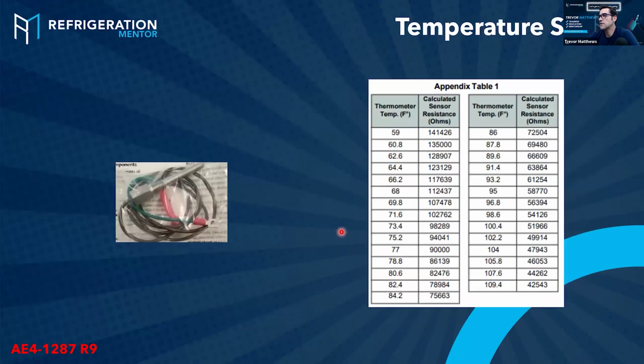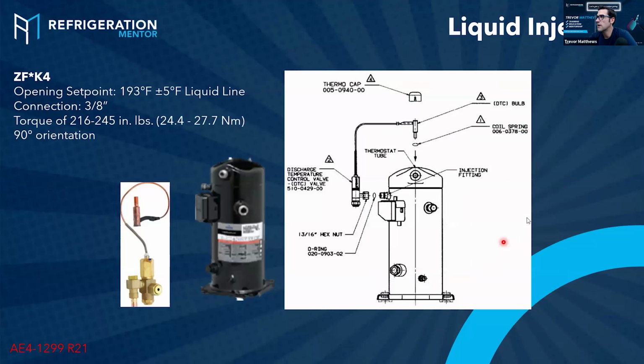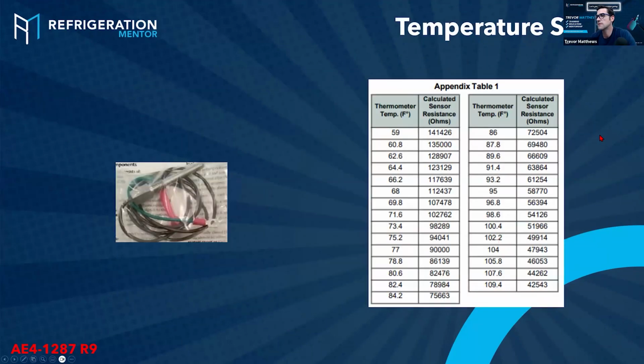Okay, let's keep going. And then here's the resistance chart. So this is kind of one of the resistors that you would screw into the head of the compressor. You would need to put some either Nylog or some thermal paste on there, which is really good. And then here's the sensor resistance. So at 90,000 right here, 77 Fahrenheit or 25 degrees Celsius. I'm not going to get into liquid injection yet on scrolls, but we'll talk about that in a few minutes here.